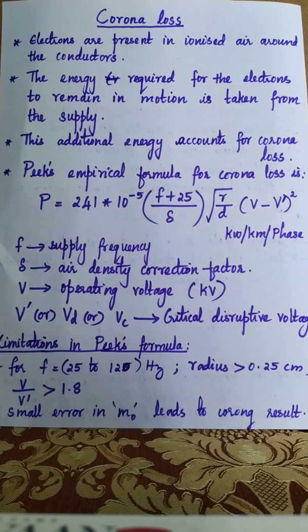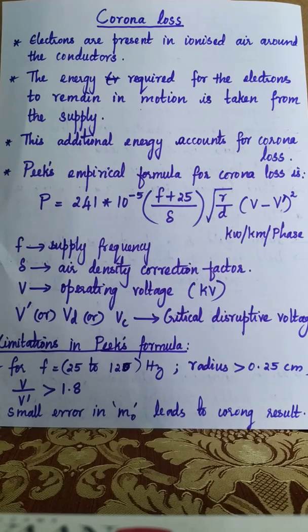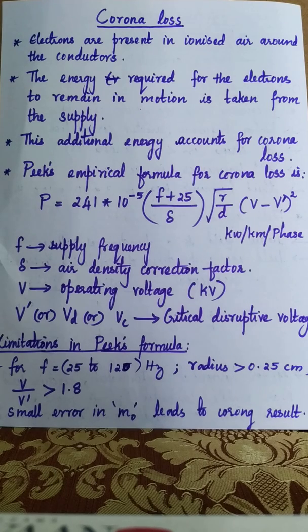Here, f is the supply frequency, δ is the air density correction factor, V is the operating voltage in kilovolt, and V' (also denoted Vd or Vc) is the critical disruptive voltage. The energy taken by free electrons from the supply system to maintain motion and strike other air molecules to produce an avalanche of free electrons is called corona loss.